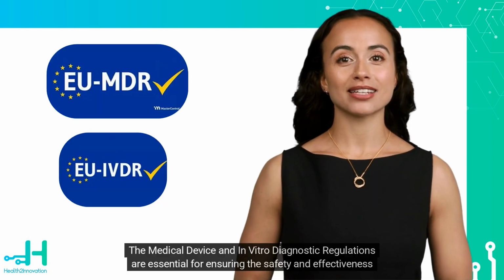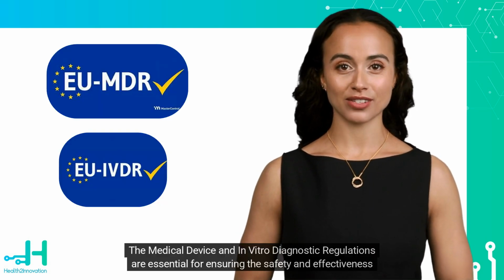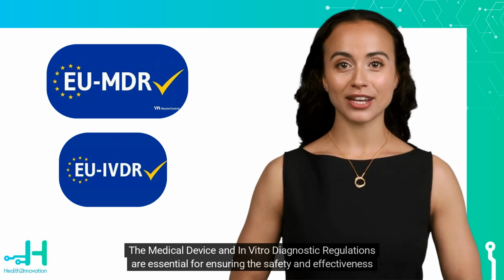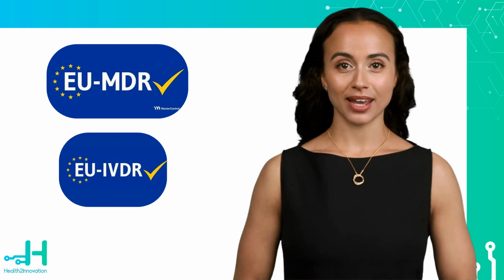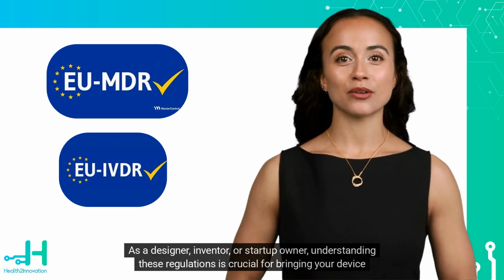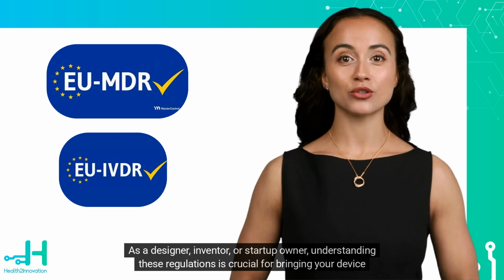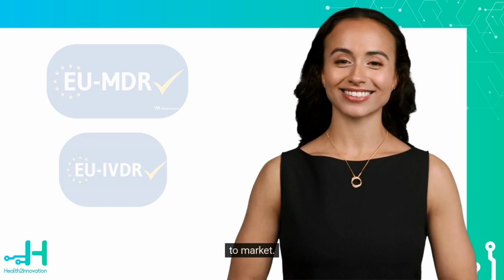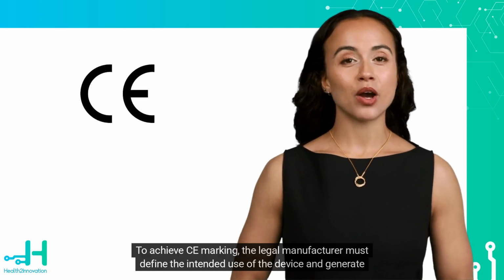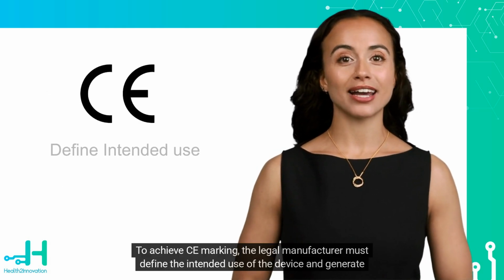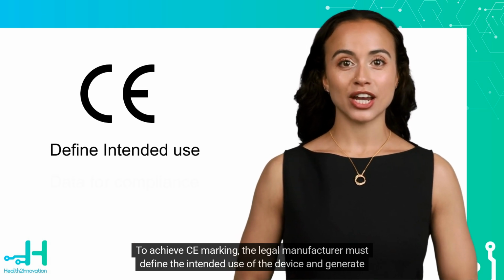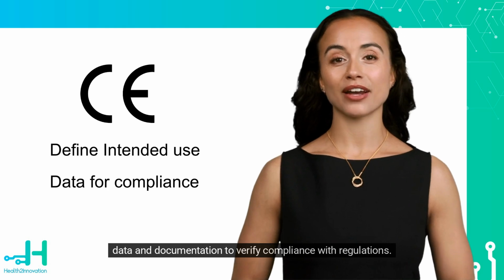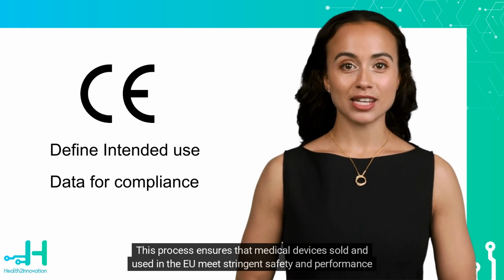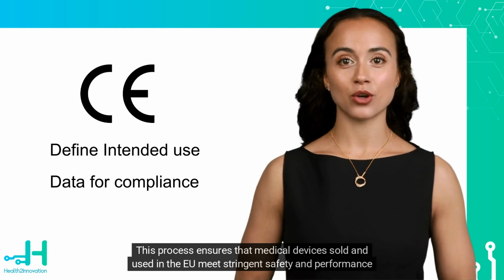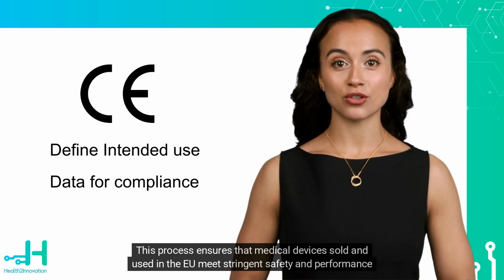The medical device and in vitro diagnostic regulations are essential for ensuring the safety and effectiveness of medical devices. As a designer, inventor, or startup owner, understanding these regulations is crucial for bringing your device to market. To achieve CE marking, the legal manufacturer must define the intended use of the device and generate data and documentation to verify compliance with regulations. This process ensures that medical devices sold and used in the EU meet stringent safety and performance standards.